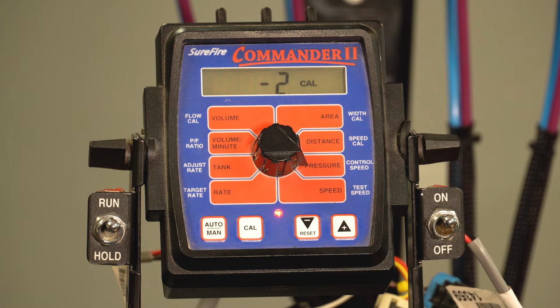And this would be the number that essentially would tune the system in a little bit tighter if we were going too fast or going too slow, if we were over adjusting. It would kind of dial that in tighter. So again, the factory setting there is going to be -2 for both our electric pump systems and our hydraulic pump systems. But be sure to reflect back to your specific manual for other platform values.